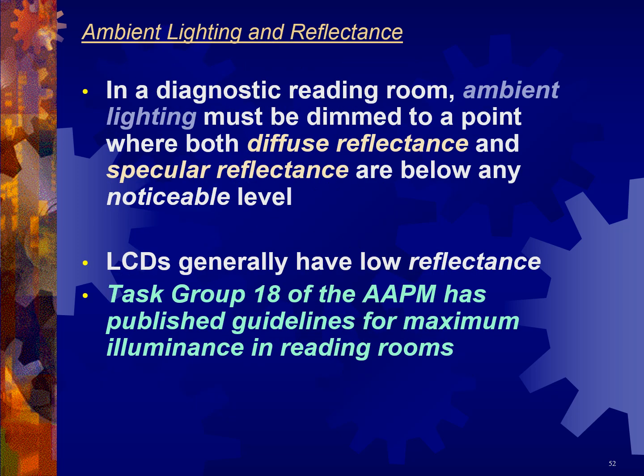Right. So because both specular and diffuse reflections are bad because they affect our ability to actually view the X-ray we're trying to view, ambient light sources must be kept to a minimum in a radiologist's reading room.